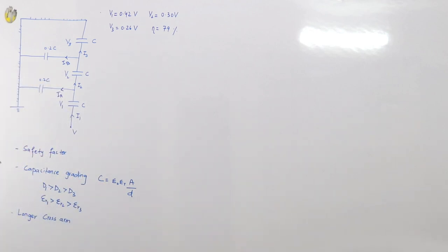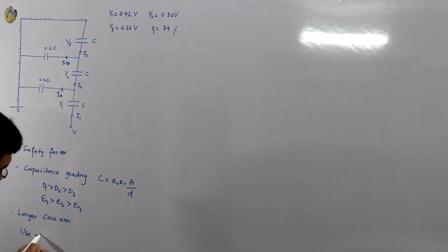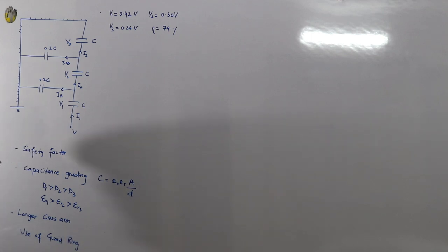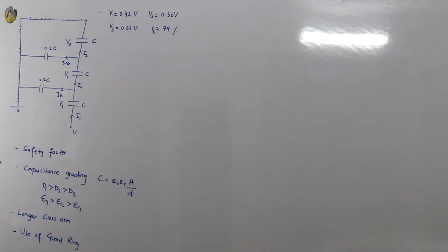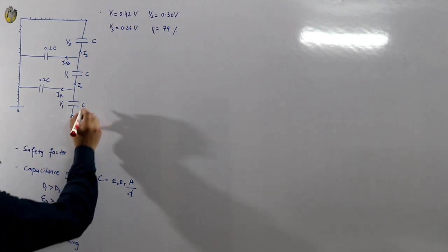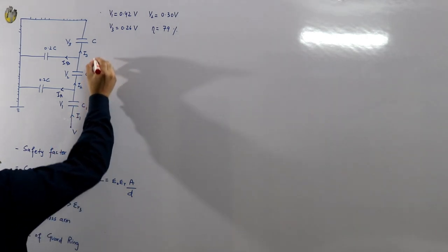The practical method is the use of a guard ring. A guard ring is basically a toroidal — more precisely an elliptical — metallic electrode provided at conductor potential. You can also mathematically find the values of the capacitances needed, for example labelling the mutual capacitances as C₁, C₂, C₃ for a capacitance grading analysis.